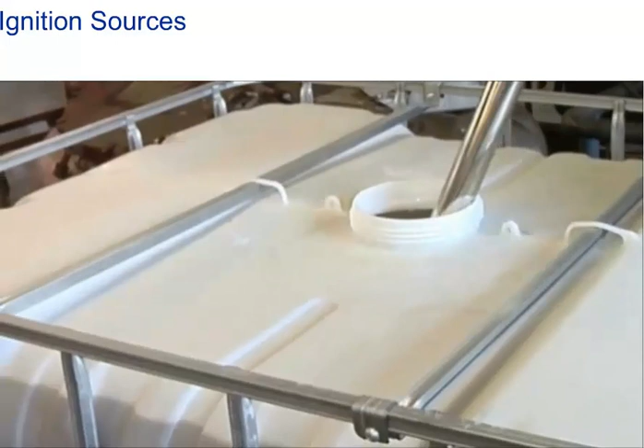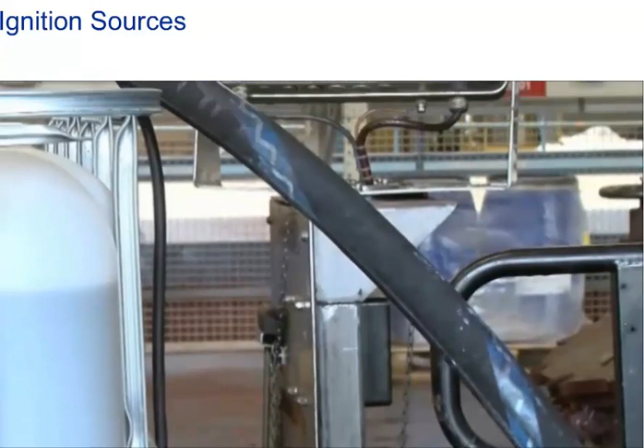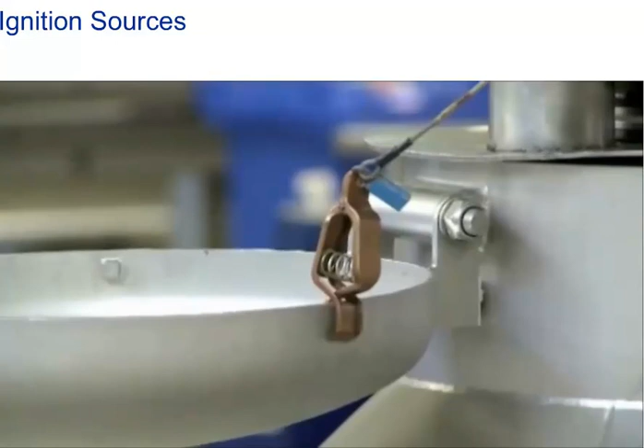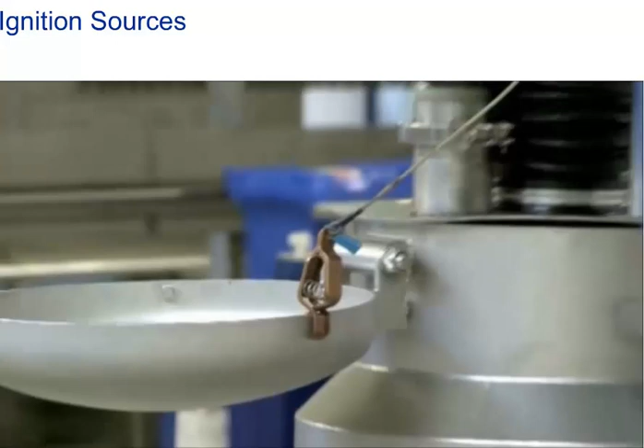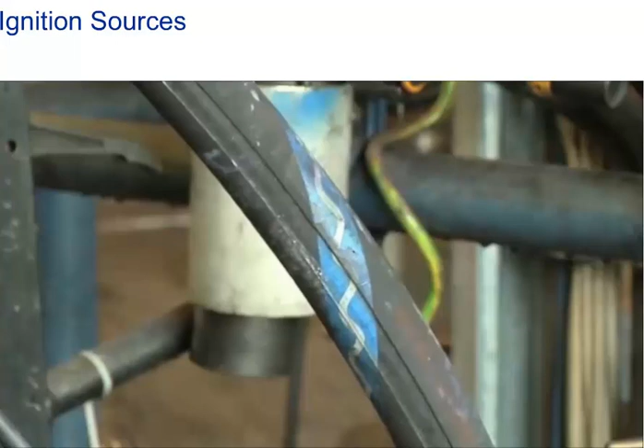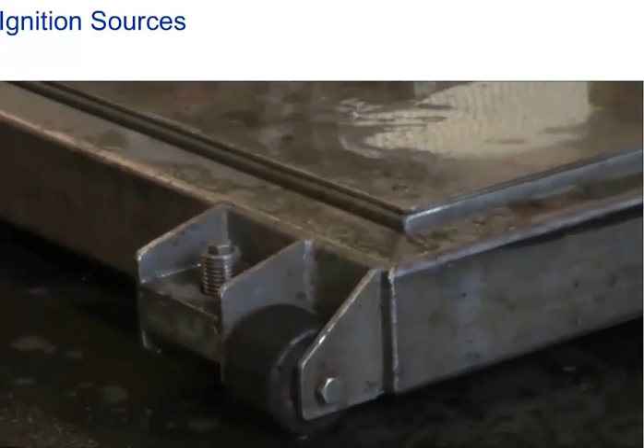Static electricity also builds up when solids or liquids are transported through pipework or during packaging operations. Effective protective measures to prevent static electricity take the form of earthing machines and equipment, and eliminating the use of insulating materials, for example, by using conductive or anti-static tubing, flooring or wheels. Furthermore, flexible parts should be kept as short as possible.